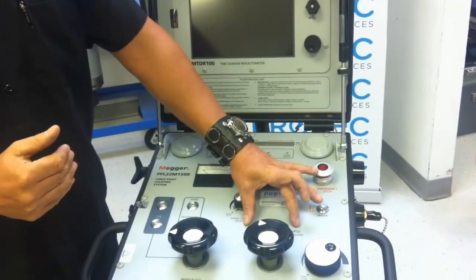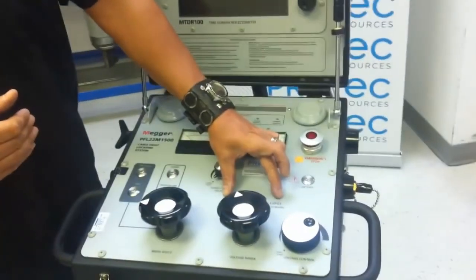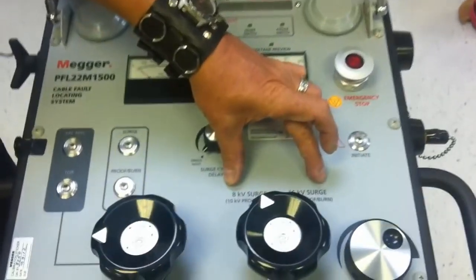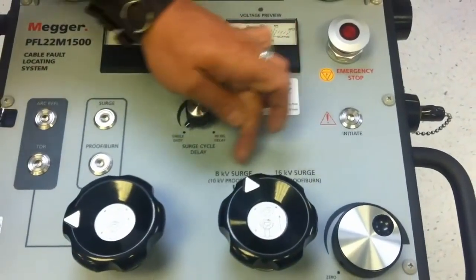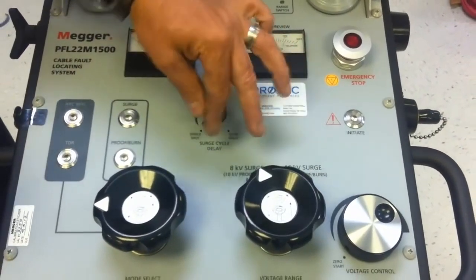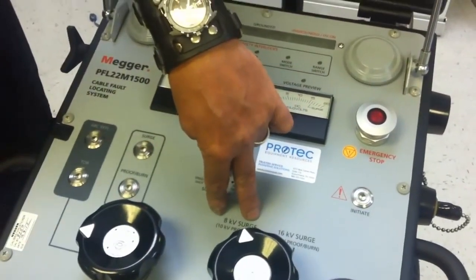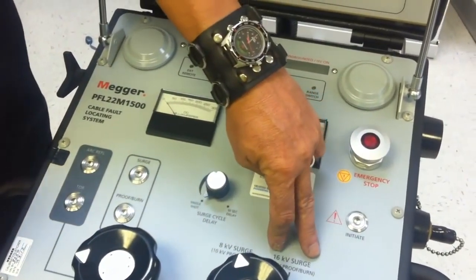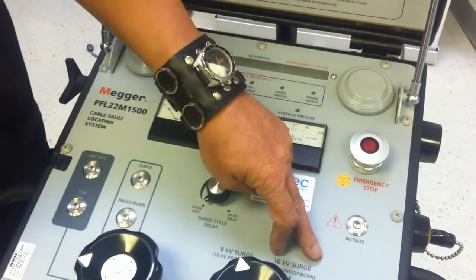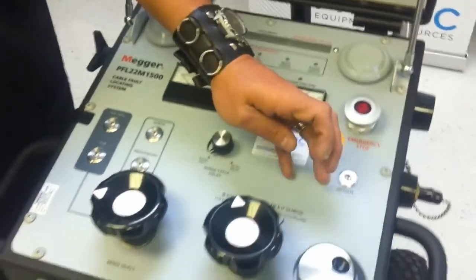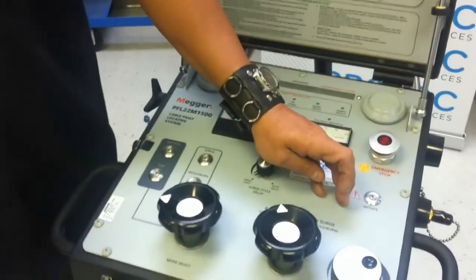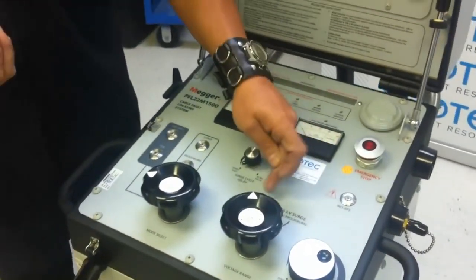So we have two ranges, 0 to 8,000 volts and 0 to 16,000 volts. Both will set different capacitive values. The lower thumping range uses the larger capacitance. The higher thumping range uses a slightly lower capacitance, delivering the same total amount of energy of 1,500 joules at the maximum output of either range.